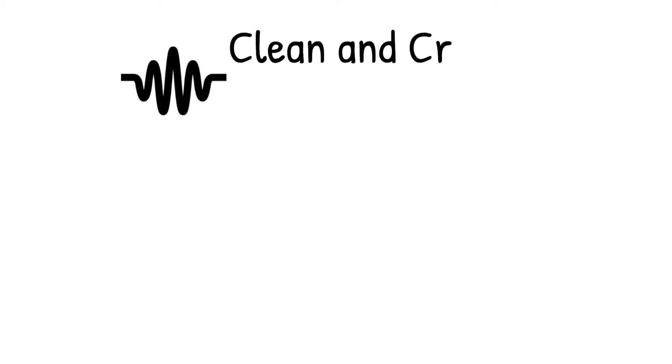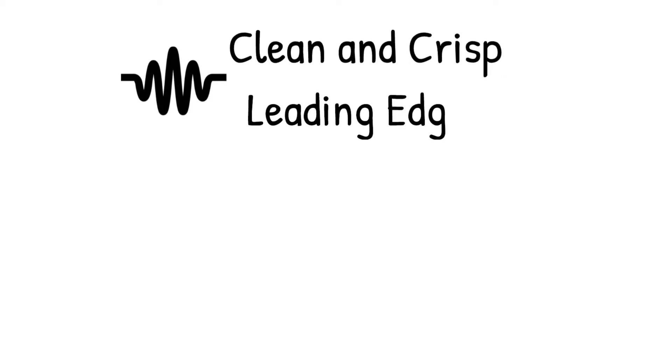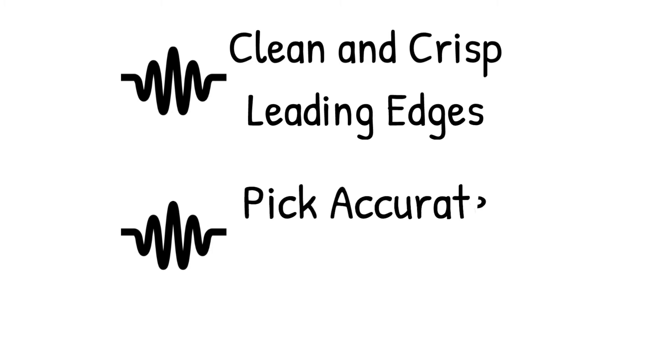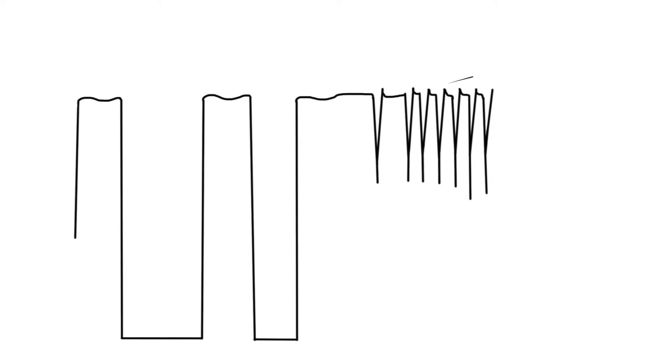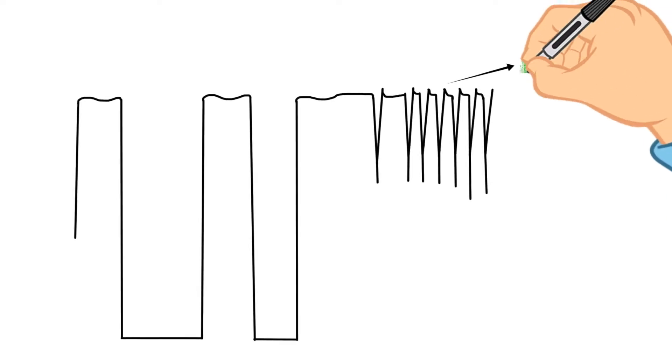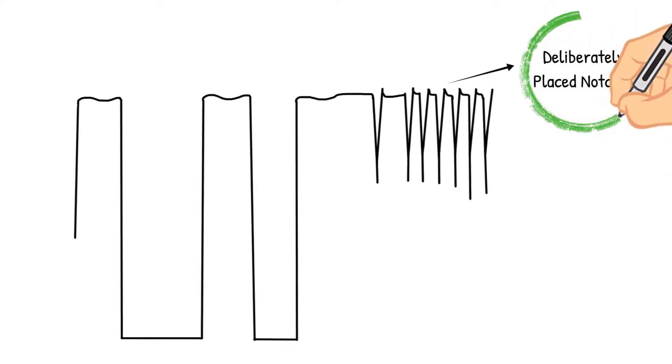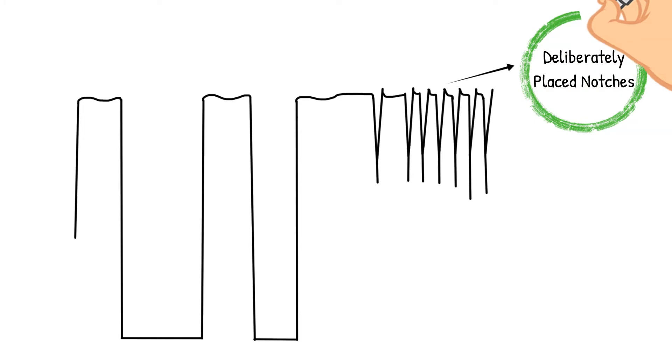Boonton's superior rise time allows for clean and crisp leading edges of pulses within the waveform and permits the user to pick a more accurate starting point on the leading edge of the pulse. The pulse train of SSR signals contains deliberately placed notches that rely on clear-cut timing to determine the requested information.